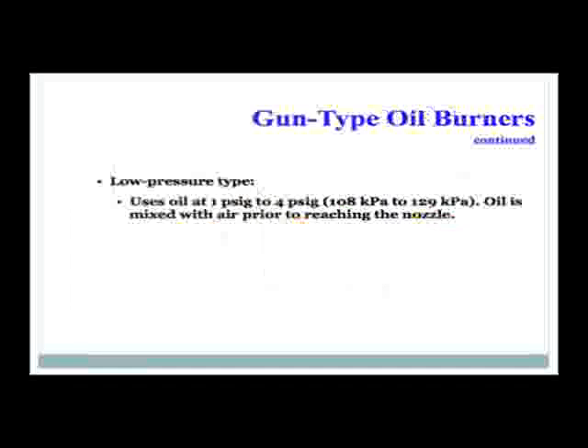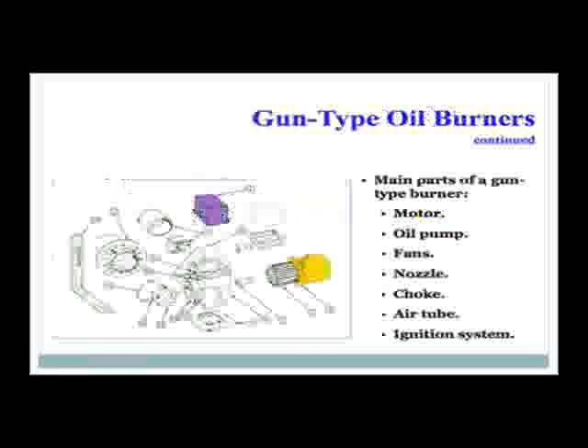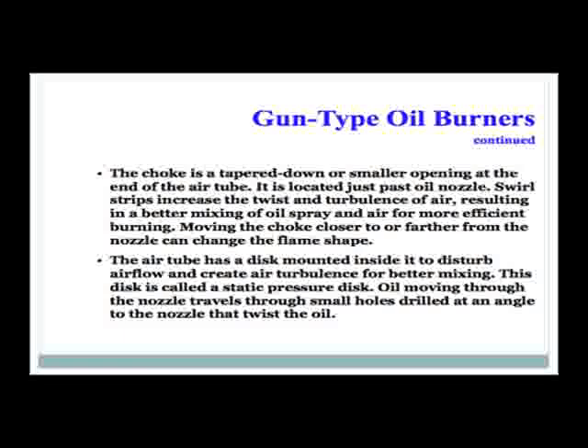The low-pressure type uses oil at 1 to 4 PSI, and oil is mixed with air prior to reaching the nozzle. The main parts of a gun burner are the motor, oil pump, fan, nozzle, choke, air tube, and ignition system. The choke is a tapered or smaller opening at the end of the air tube, located just past the oil nozzle. A swirl strip increases the twist and turbulence of the air, resulting in better mixing of oil spray and air for more efficient burning. Moving the choke closer to or farther from the nozzle can change the flame shape. The air tube has a disc mounted inside it — called a static pressure disc — to disturb airflow and create turbulence for better air mixing. Oil moving through the nozzle travels through a small hole drilled at an angle that twists the oil.